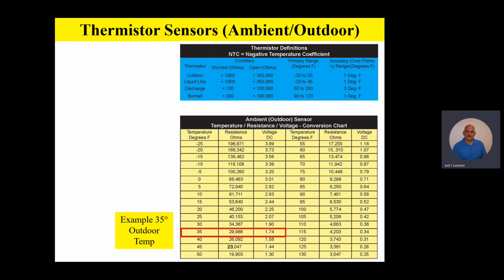Now remember, team, this is within a few points of tolerance. So in other words, if it read 29,500, it's close enough. If it read 30,000 ohms, that's close enough. You get the idea. It just isn't rocket science, so to speak. So it needs to be very close to that reading. But if it's a little bit off, don't worry about it.